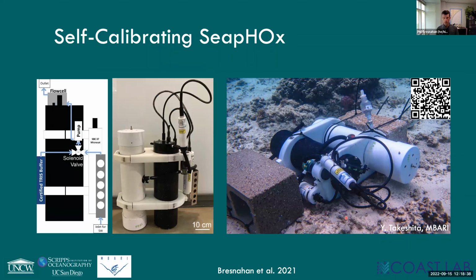One of the approaches that we've been working on recently, this is a collaboration that I was working on when I was back at Scripps Oceanography, also with Yui Takeshita up at MBARI, and my former group back at Scripps, with Todd Martz. Taylor Worth led the engineering for all of this. The goal was to add this external reagent, a tris in artificial seawater reagent, to the standard SeapHOx, the combination of that DuraFet with a bunch of other instruments, and see if we could use this reagent to periodically, autonomously calibrate the SeapHOx sensor. And so that's what you see here.